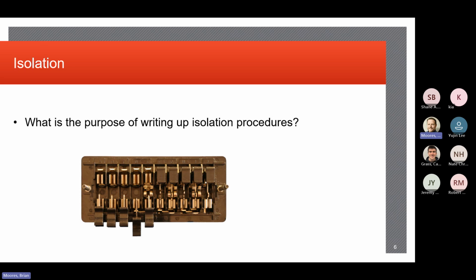So we spend a lot of time looking at the drawings, looking at the I/O diagrams, writing up those procedures. I think I mentioned last week that it probably will take longer to write up an isolation procedure, and have someone check it and go through that QA/QC process, than it would be to actually isolate and test a relay. But that's what it takes. Because we live in a CYA world, we want to make sure, A, we keep everybody safe, 100%. B, we don't want to trip off something or cause a misoperation. We should know and probably would understand what's hanging off that transformer or that bus, whether it's a hospital, an airport, could be residences. It could be a whole industrial complex, warehouse, Amazon data center. We don't know, but the reality is, we don't want to disrupt that power. So we spend a lot of time writing up those procedures and then using these test switches to isolate. So, all right. Any questions on that so far?